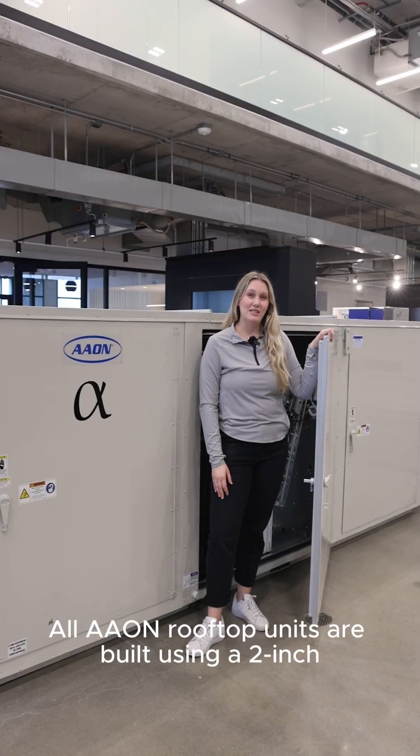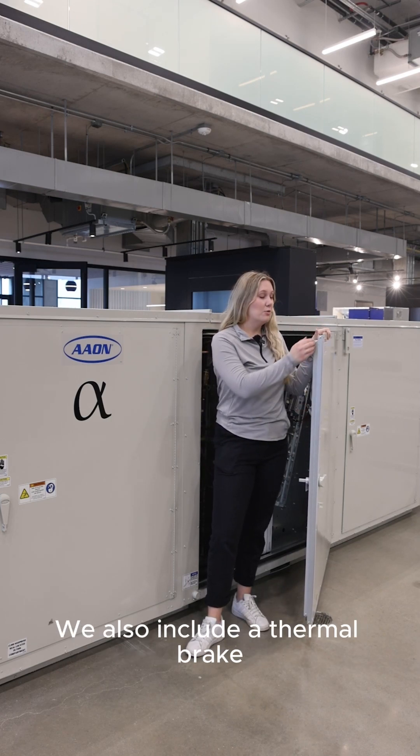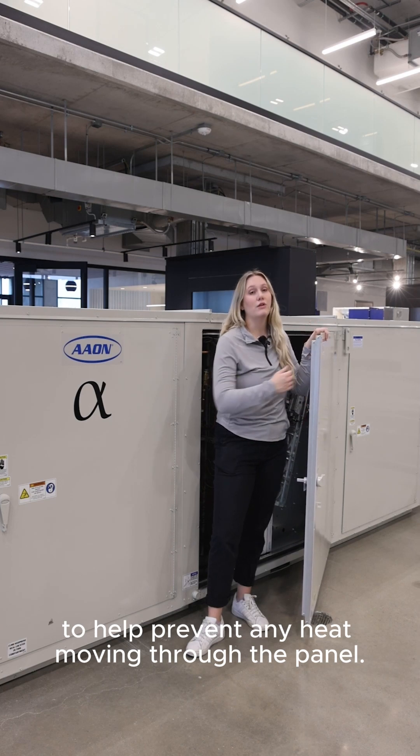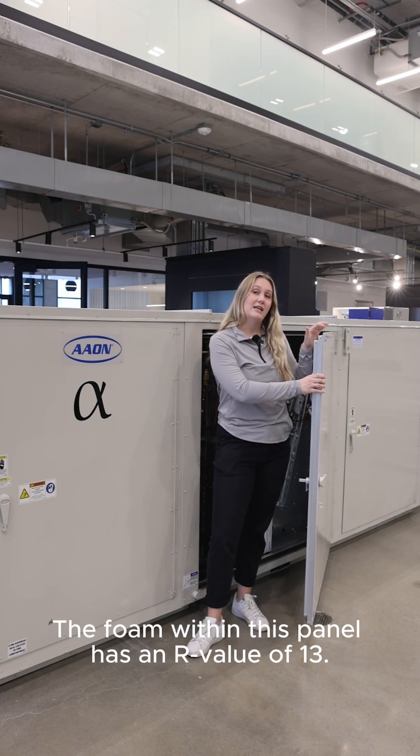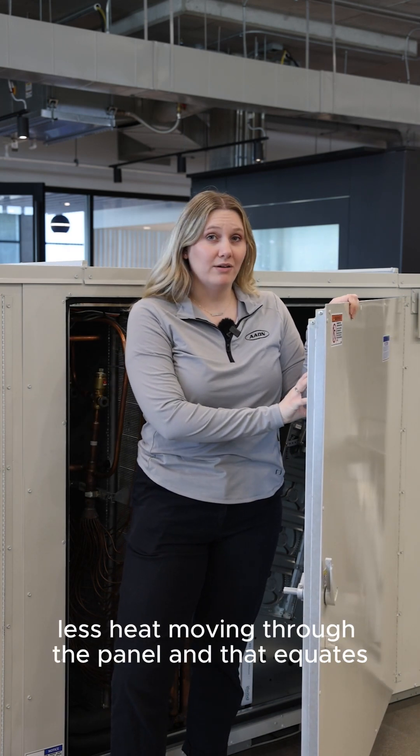All AAON rooftop units are built using a 2-inch polyurethane foam injected panel. We also include a thermal break to help prevent any heat moving through the panel. The foam within this panel has an R-value of 13.